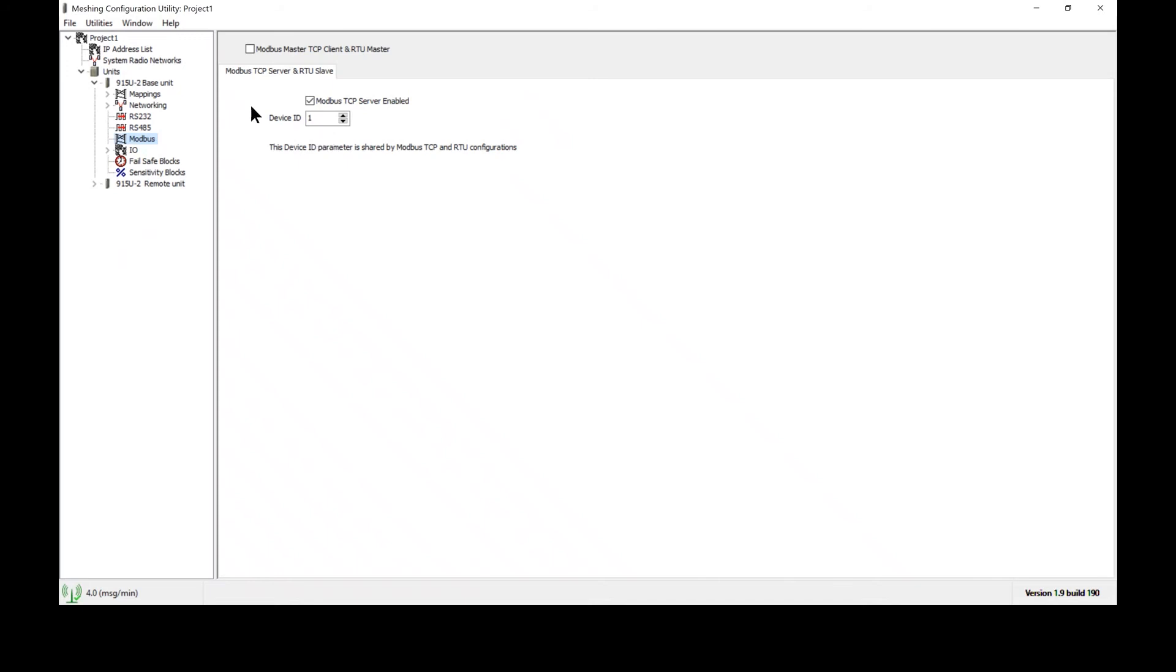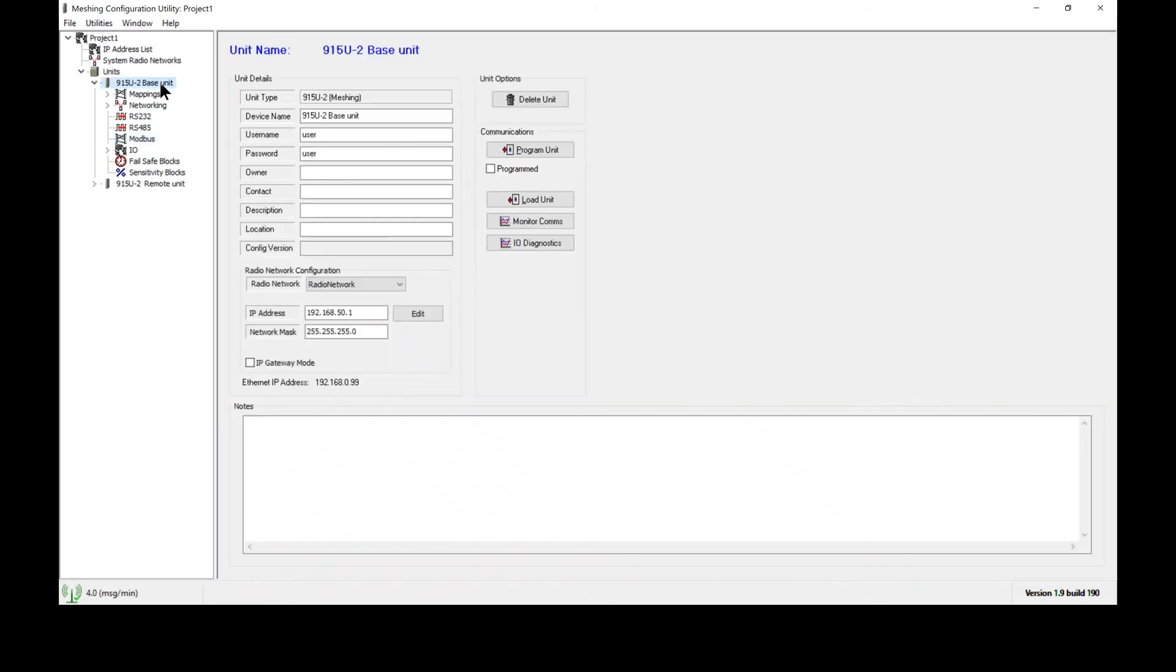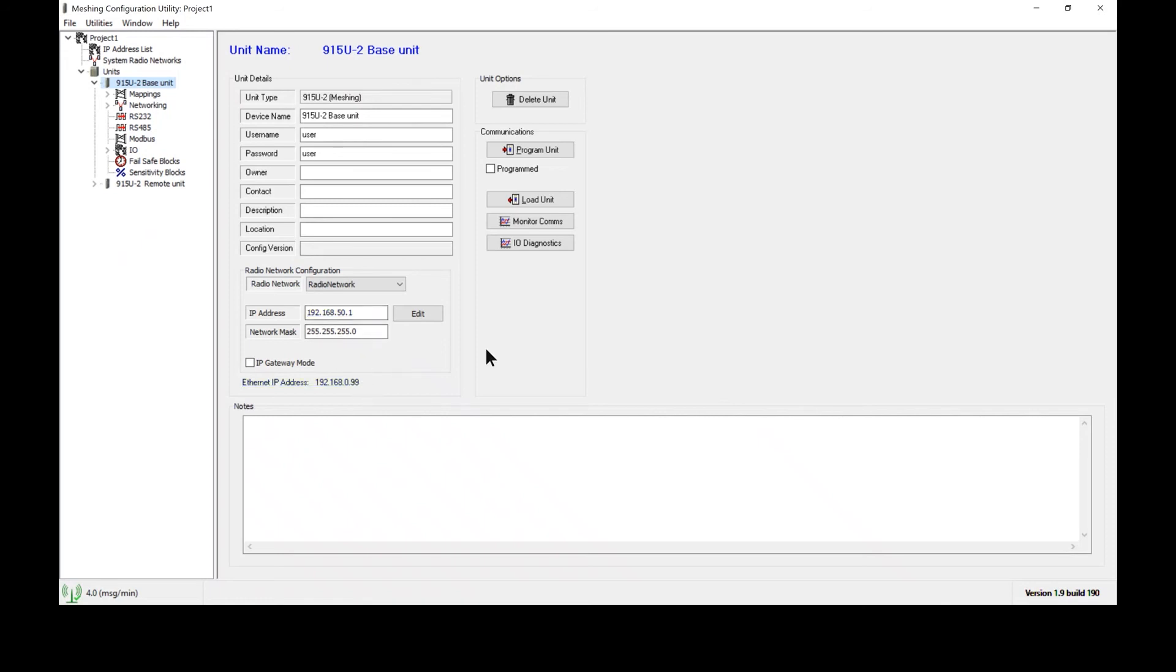The addressing is done via IP address. Now note with the 915U2 there's two IP addresses: the radio port and the Ethernet port. These two ports are not bridged together for security reasons and for other design purposes. The Ethernet port is the IP address that we will use to do our Modbus communications.